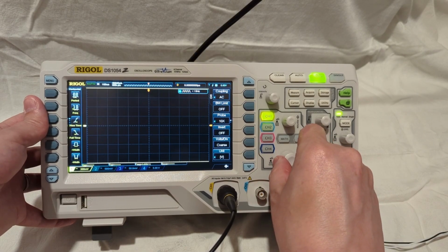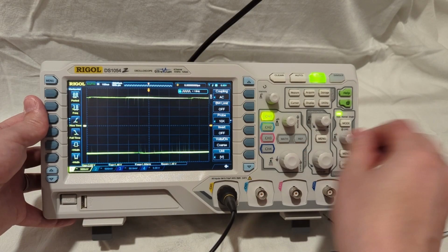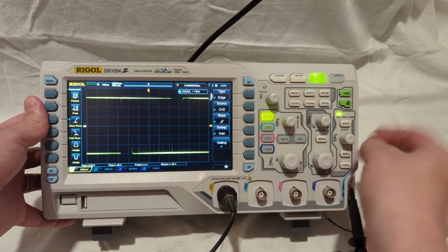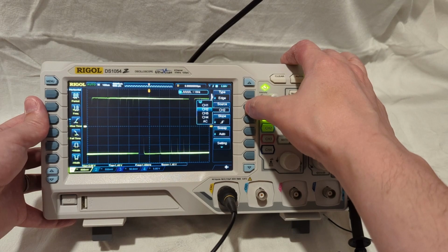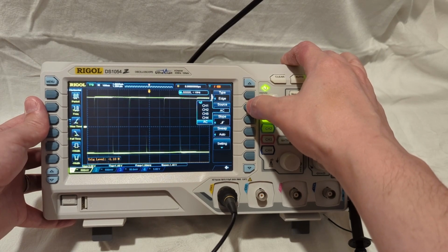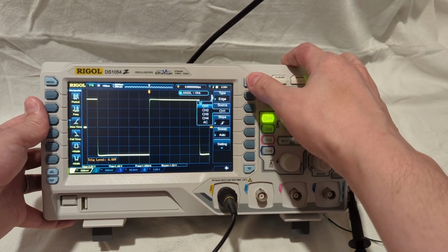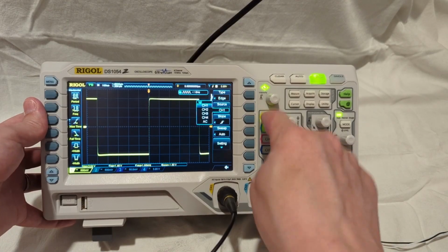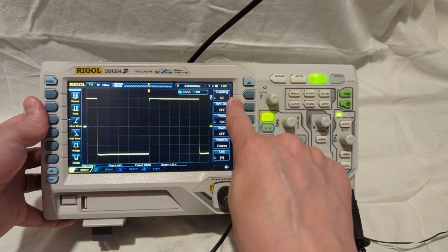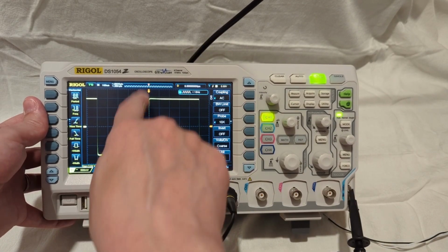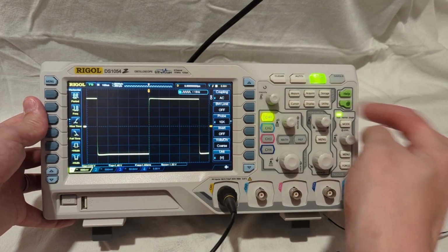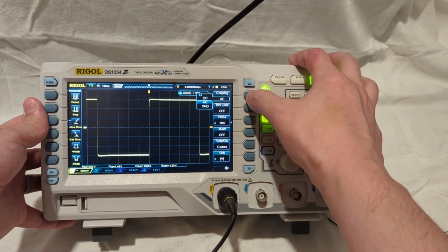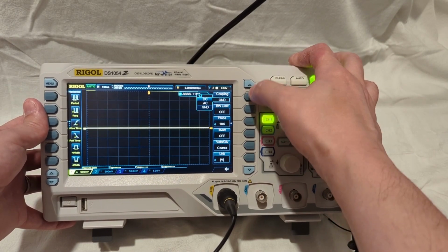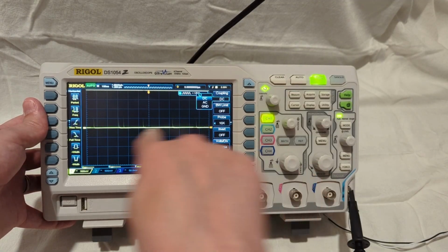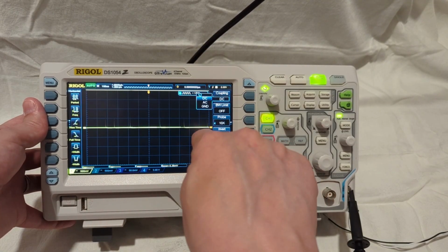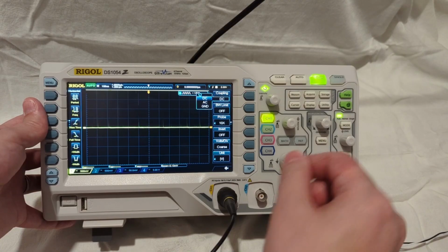We can adjust this, and now we need to go in and change my trigger to channel 1. Now that'll get it to trigger correctly. And channel 1 I currently have set to AC coupling, so that's going to be oscillating around 0. But if I change that to a DC coupling, we will see that that signal has a 0 level that is at 0 volts, and the upper level is at a higher level.